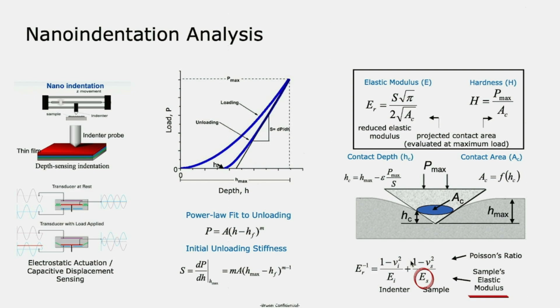The elastic modulus is defined by the contact stiffness divided by the area. The contact stiffness is defined by the slope of the unloading curve, and the contact depth also comes from the Oliver and Pharr model. And hardness is quite similar to Vickers hardness. This is the maximum force divided by the projected contact area. So the difference between nanoindentation and the Vickers indenter is that we can tell the customer the elastic behavior, just like Young's modulus. We can tell the customer the hardness as well.